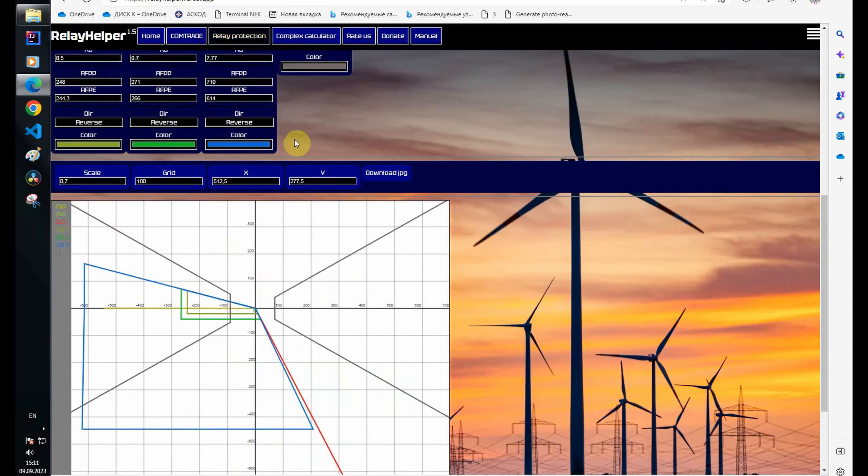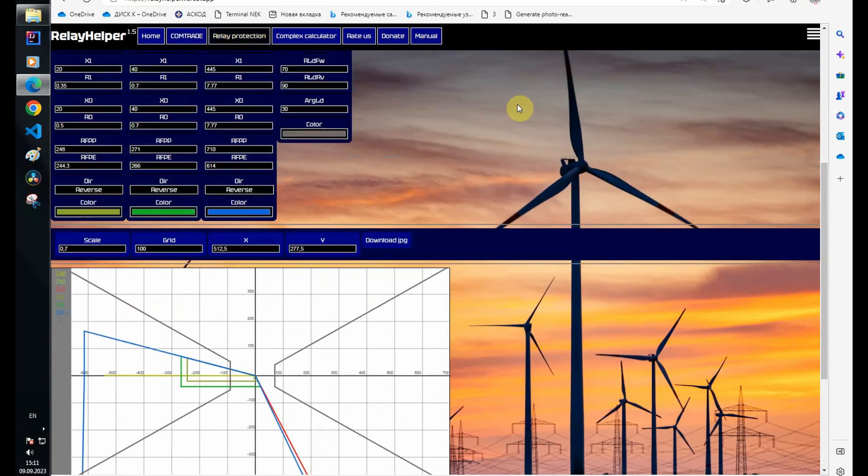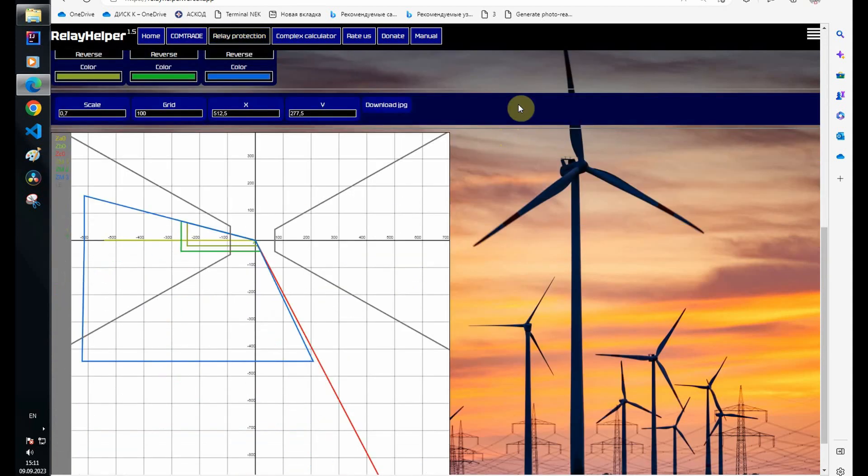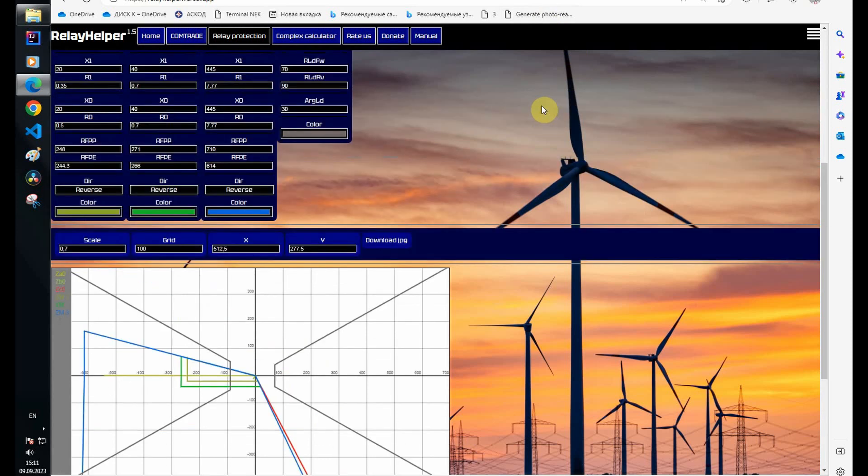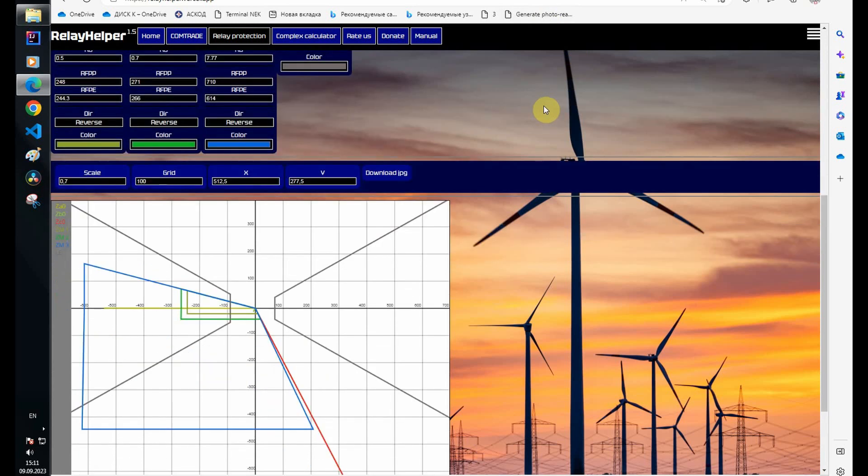I also want to say a few words about distance protection from ABB. If you noticed, there is no zero sequence current in the impedance calculator. The fact is that compensation when calculating impedance during a single phase fault is carried out by expanding the zones.